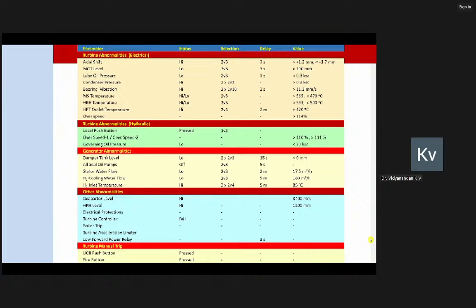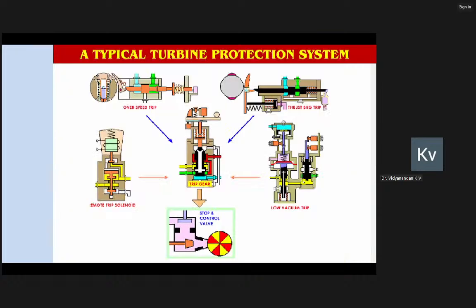So how does the protection work? The master device for the protection, every turbine will have a master trip device, the so-called trip gear. In BHEL or Siemens terminology, we call it a trip gear, whereas in Russian terminology, they call it by some other name. Whatever name you give, it is the source of that power oil which is responsible for the operation of the stop and control valve. In our Siemens terminology, we call it the trip oil.